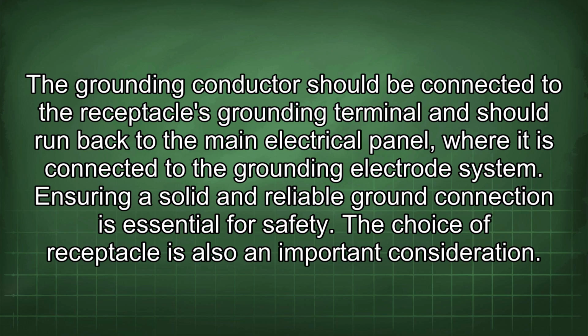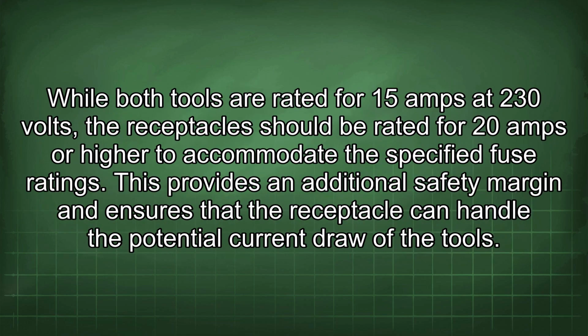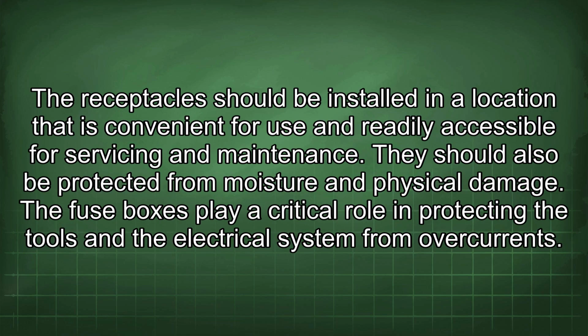The choice of receptacle is also an important consideration. While both tools are rated for 15 amps at 230 volts, the receptacle should be rated for 20 amps or higher to accommodate the specified fuse ratings. This provides an additional safety margin and ensures that the receptacle can handle the potential current draw of the tools. The receptacle should be installed in a location that is convenient for use and readily accessible for servicing and maintenance. They should also be protected from moisture and physical damage.